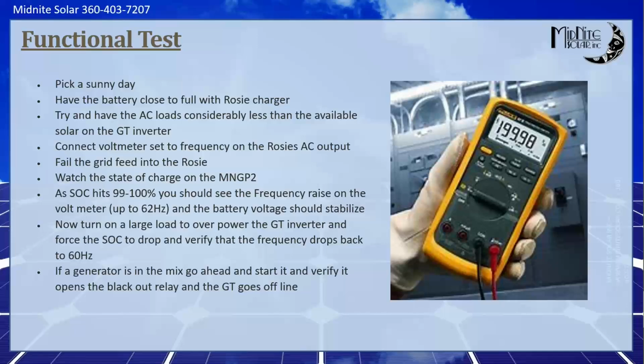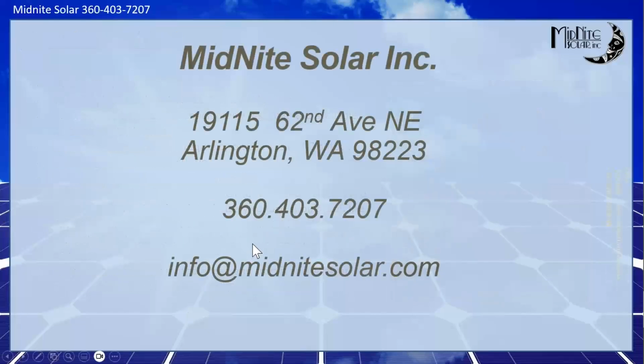And if you have a blackout relay on a generator, also a great time to test that. Make sure that when that generator starts, the grid tie inverter goes offline instantly. That's a pretty simple test, but just verify that. And that's kind of it.